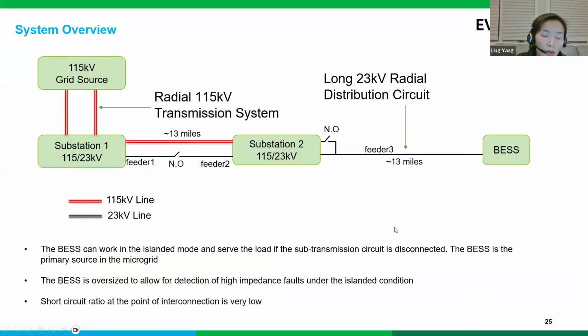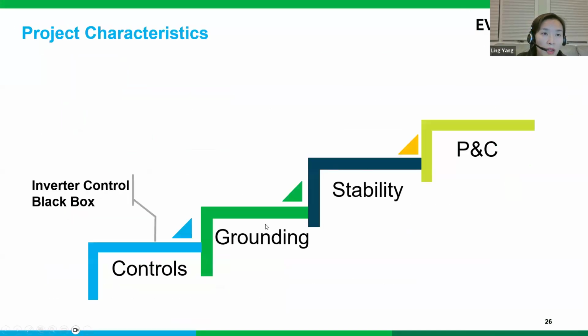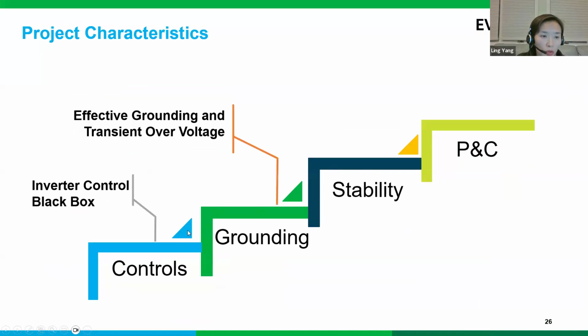Design challenges. We met a lot of design challenges. I want to talk about this one first. First of all, this is one of the first of its kind, and this is the first microgrid project for Eversource. For the grid forming inverters, the control inside is kind of a black box, which is very new to us. And also during the design phases, how we ground the systems. At the very beginning, we found there were effective grounding and transient overvoltage, and we spent quite a lot of time trying to mitigate the transient overvoltage.